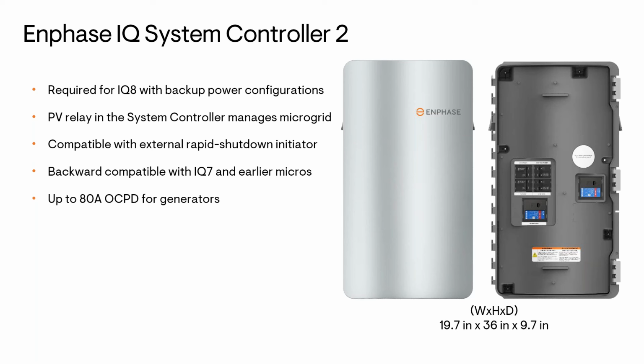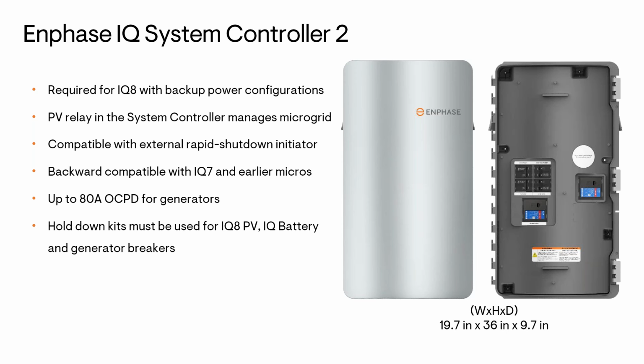It can accommodate up to an 80 amp breaker for generators, whereas the first generation could accommodate just a 60 amp breaker. So you could connect potentially larger generators and get more power from those generators. And hold-down kits are also required in the system controller 2 for the PV circuit, battery circuit, and if there's a generator integrated, it also must have a hold-down kit because they're reverse-fed breakers.